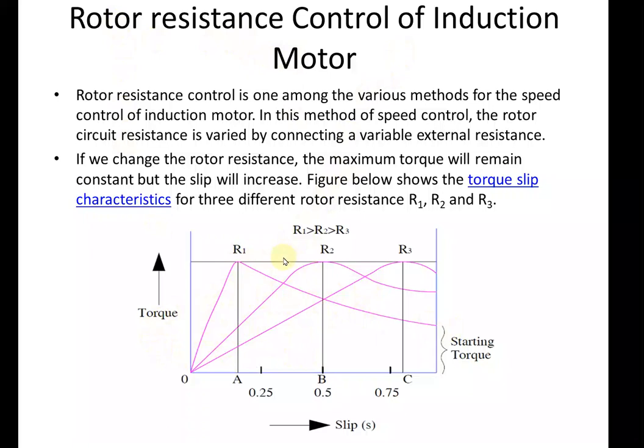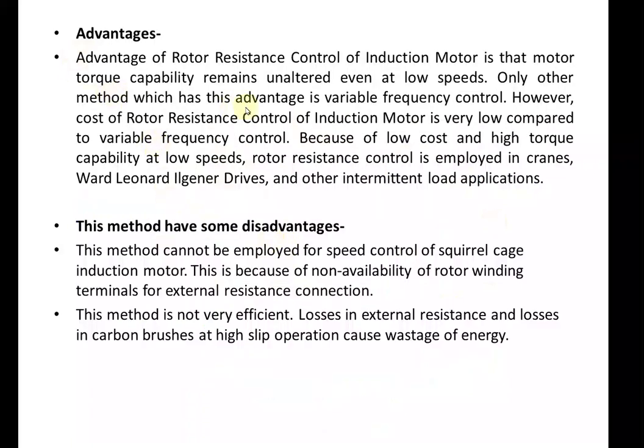The main advantage of this method is that the motor torque capability remains unaltered or unchanged even at low speeds — torque is constant. The cost of this method is very low as compared to the variable frequency drive. Because of this low cost and high torque capability at low speeds, it is employed in applications requiring high starting torque, such as cranes, Ward Leonard Ilgener Drives, and other intermittent load applications.